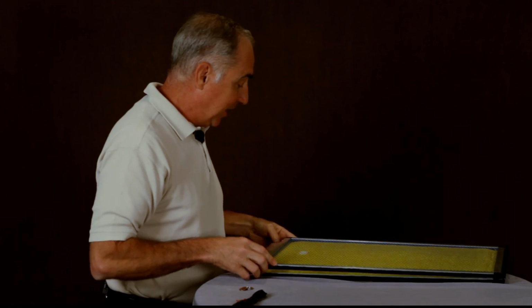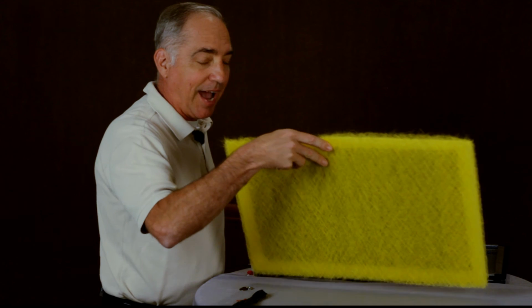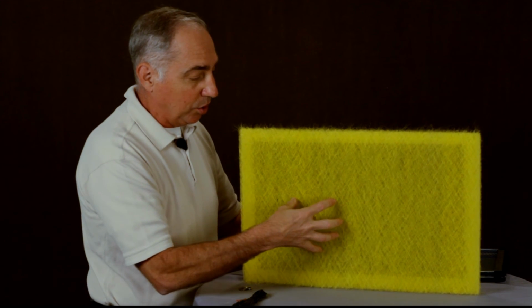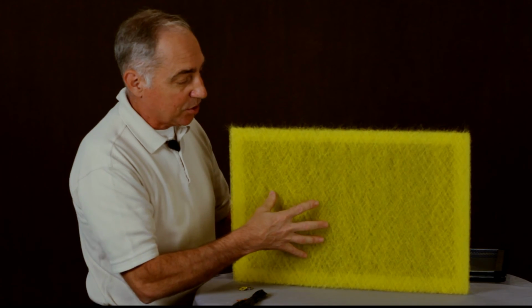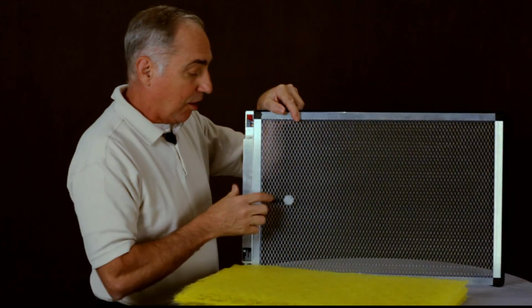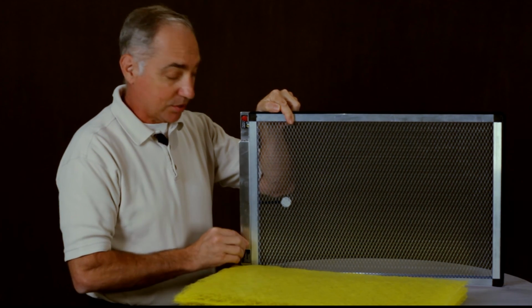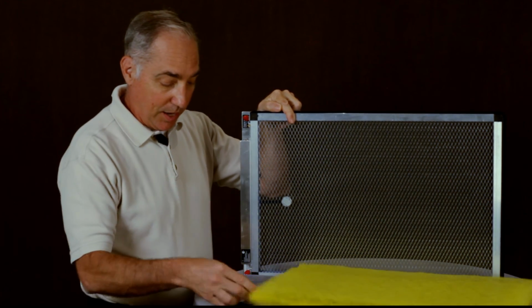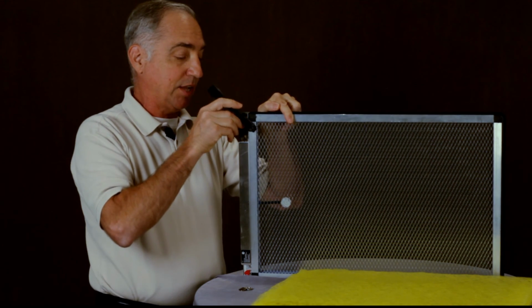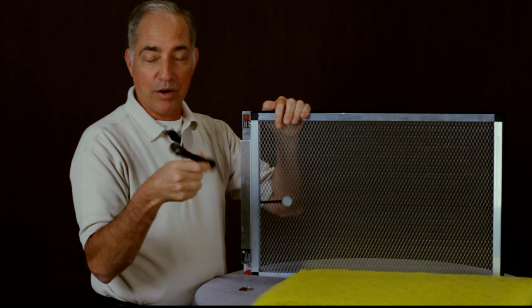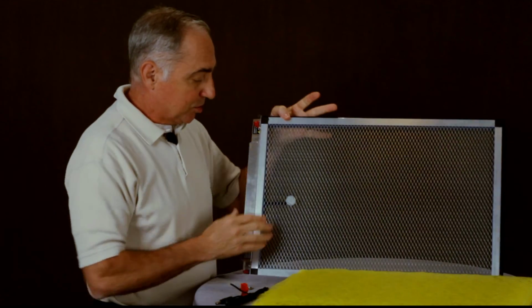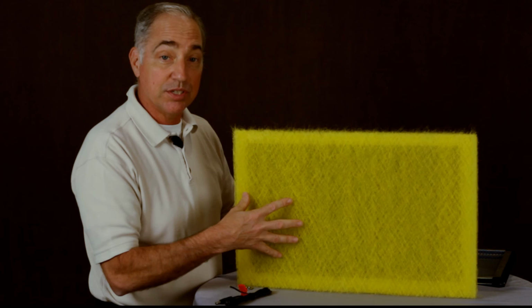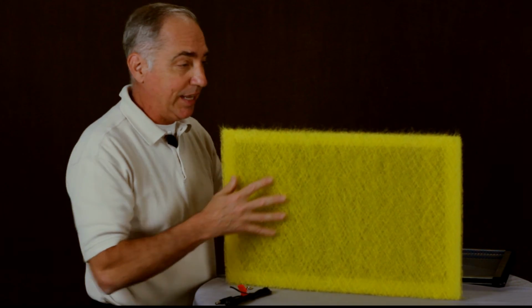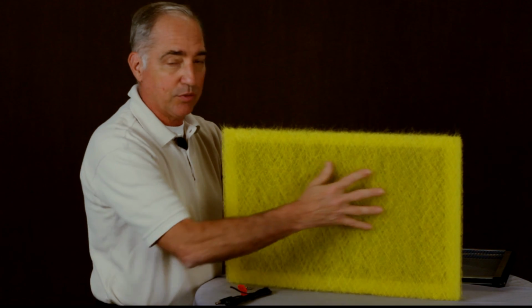So what we've got inside is a very low oil content, high glass content fiberglass with a low pressure drop carbon center screen. So what that does is it accepts the charge off the probe. We've got the 7,000 volts of energy that comes off of this power head here. And all you guys do is just wire it in, this plugs in just like a computer or a calculator, and that wires into a transformer, R and C, just wire it hot. So as that probe embeds itself, when you close this up, that probe embeds itself inside the carbon. So then carbon induces the voltage onto every fiber here equally. So we got 7,000 volts of energy running through this whole pad.